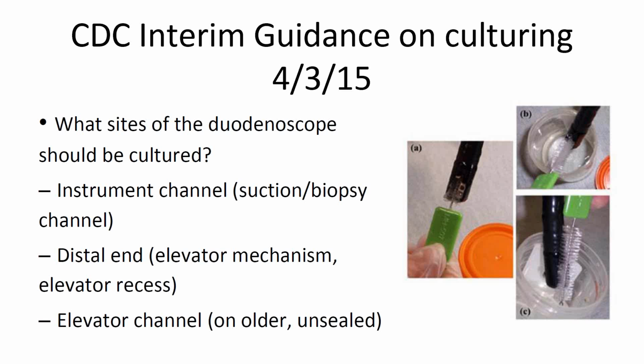So that brings us to culturing. This is a question I receive very often: should I culture my endoscopes? And there is guidance that's been put out earlier this year from the CDC. It is an interim guidance on how to culture specific to duodenoscopes at this point.